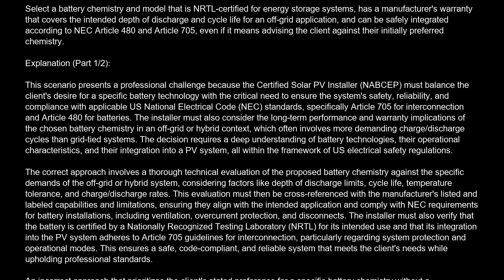The correct answer is A. Select a battery chemistry and model that is NRTL certified for energy storage systems, has a manufacturer's warranty that covers the intended depth of discharge and cycle life for an off-grid application, and can be safely integrated according to NEC Article 480 and Article 705, even if it means advising the client against their initially preferred chemistry.